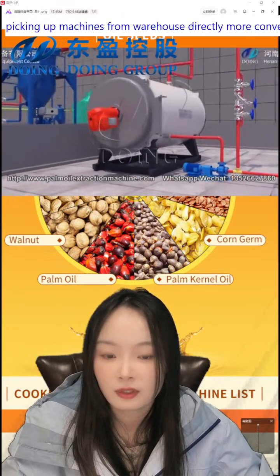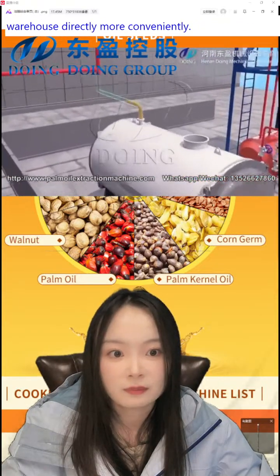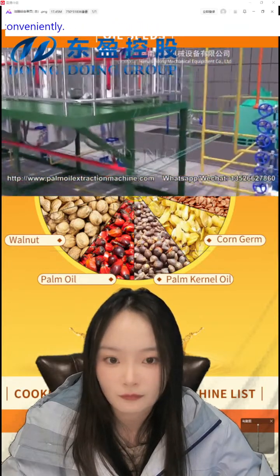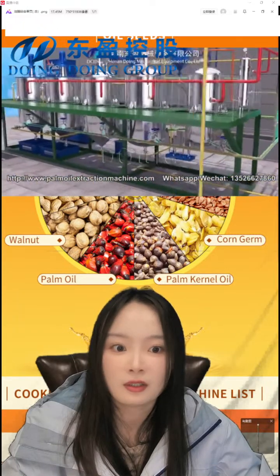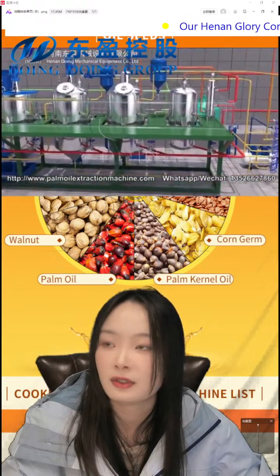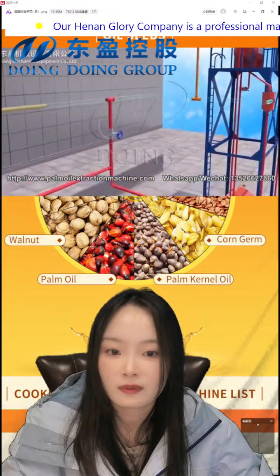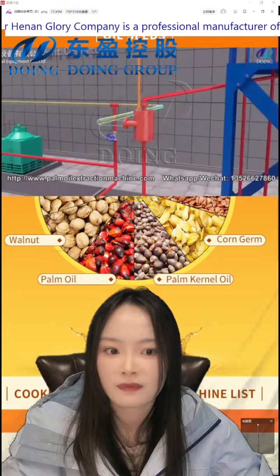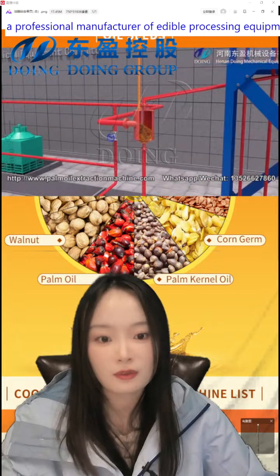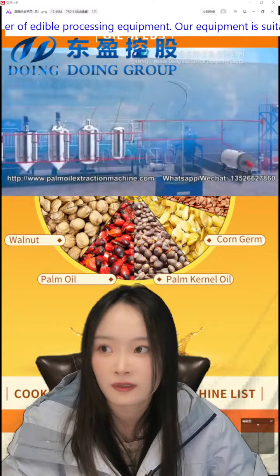The conduction oil is then piped to each section. Each section of the plant provides heat sources for the refining process. The thermal oil is recycled throughout the workshop. The thermal oil temperature is heated to about 260 to 300 degrees through the heat transfer oil furnace to provide heat source for the workshop. The use of thermal oil heating has the advantage of high heating efficiency and low cost.